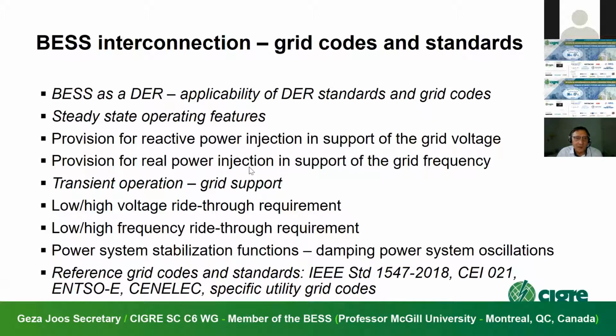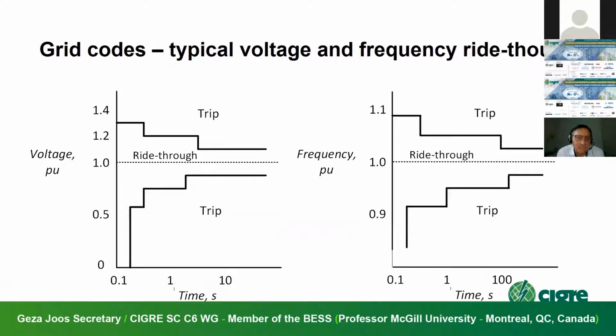Provision of reactive power and real power. And then there are the transient operating modes, which are similar to that of the DER. You have to be able to do low voltage and high voltage ride-through, and low frequency and high frequency ride-through. And there are a very large number of standards. In the US, the much talked about standard today is the 1547 2018 version. So these are examples of voltage and frequency ride-throughs. The number of levels depends upon the grid code, and the values also depend upon the grid code.